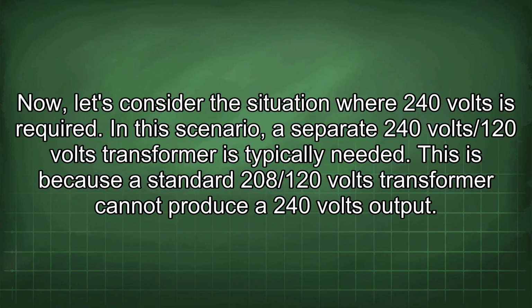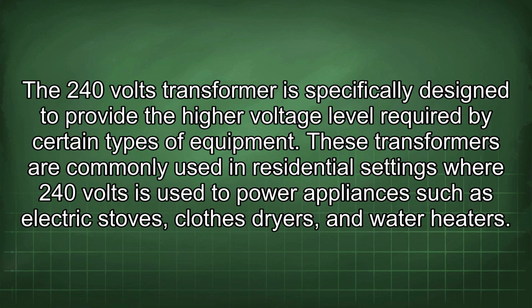Now, let's consider the situation where 240 volts is required. In this scenario, a separate 240 volts/120 volts transformer is typically needed. This is because a standard 208/120 volts transformer cannot produce a 240 volts output. The 240 volts transformer is specifically designed to provide the higher voltage level required by certain types of equipment.